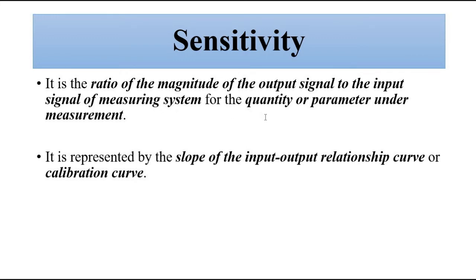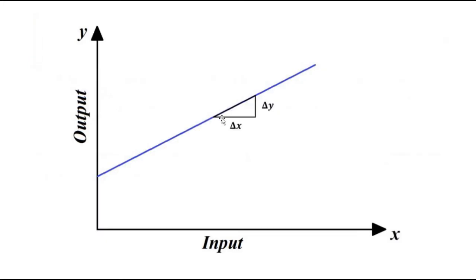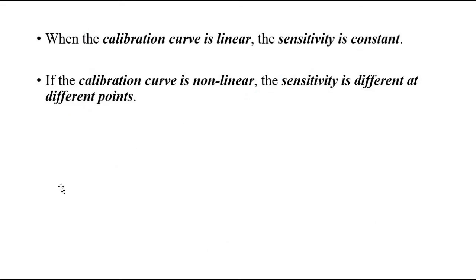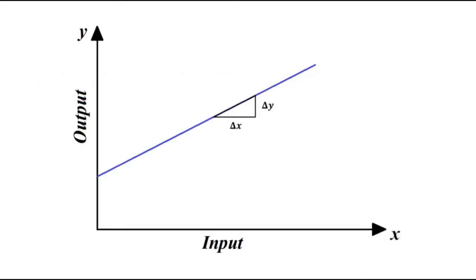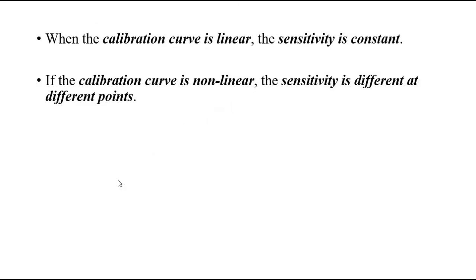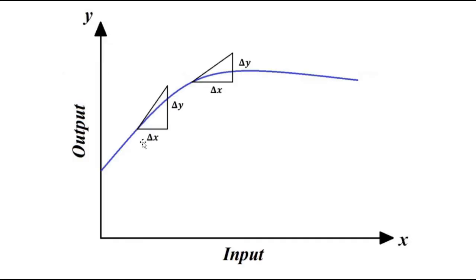Sensitivity is defined for the parameter which is under measurement. It is the slope of the input-output relationship curve, also called the calibration curve. If the input-output relationship curve is linear, the sensitivity will be fixed. But if it is nonlinear, the sensitivity will be different at different points — the slope will be different at different points, and so will be the sensitivity.